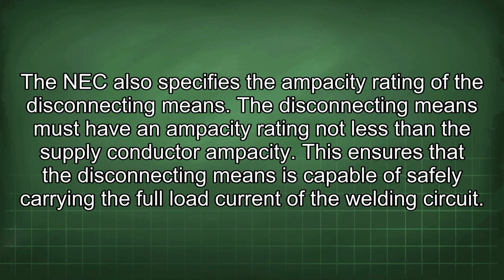The NEC also specifies the ampacity rating of the disconnecting means. The disconnecting means must have an ampacity rating not less than the supply conductor ampacity. This ensures that the disconnecting means is capable of safely carrying the full load current of the welding circuit.